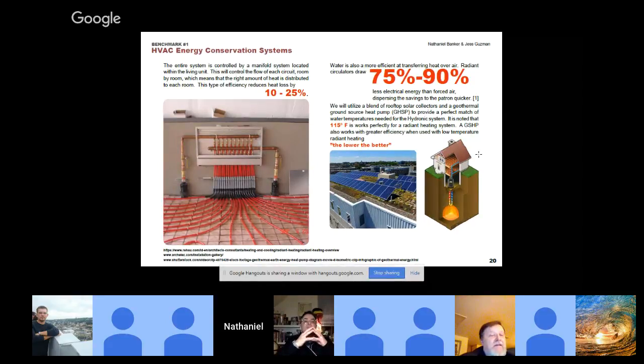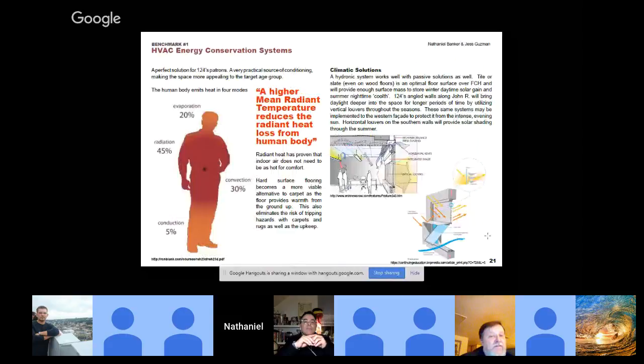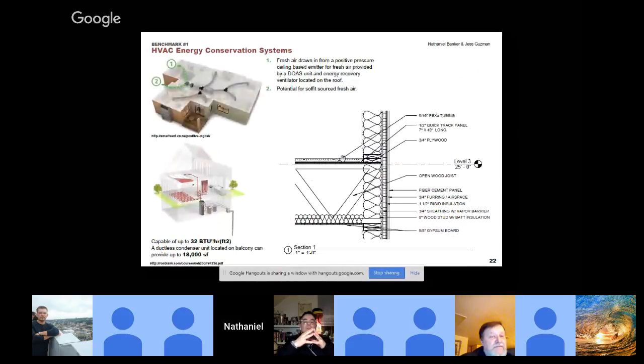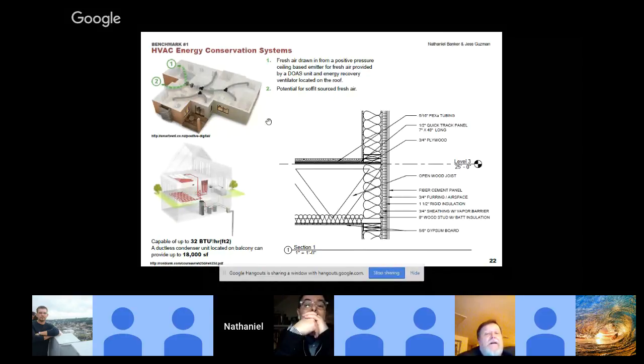Is this heating only? No, it would be cooling as well. Okay, so you know some of the issues with cooling, right? We need to draw fresh air and create positive pressure. If you have hydronic for heating and cooling, remember that sounds good, but it doesn't put any air in the building. So you need something that brings air in, like the DOAS, and probably some emitter that tempers the air as it comes in. Keep that in mind.